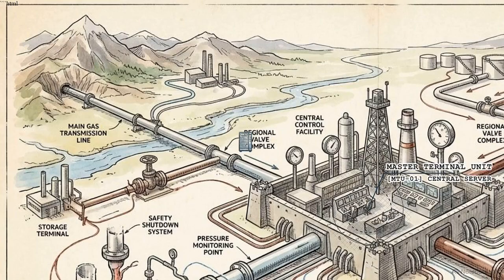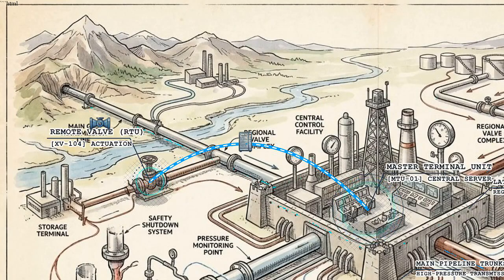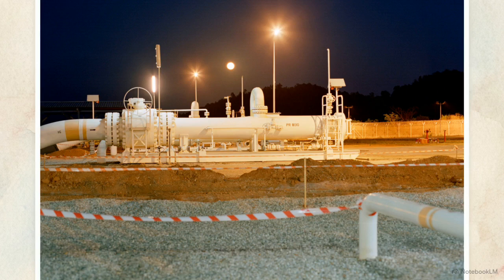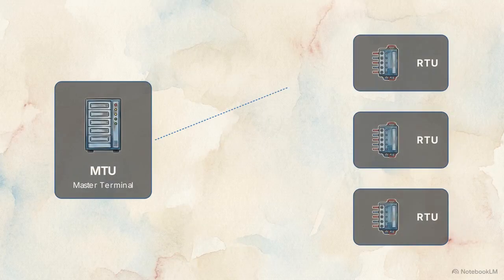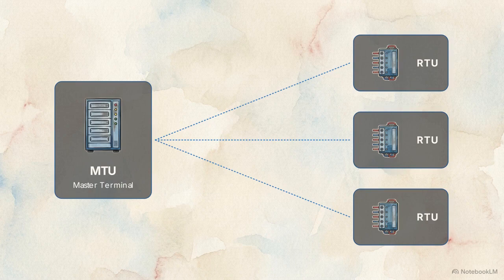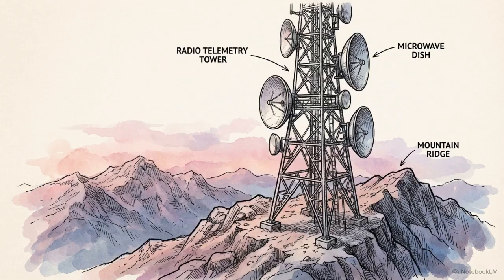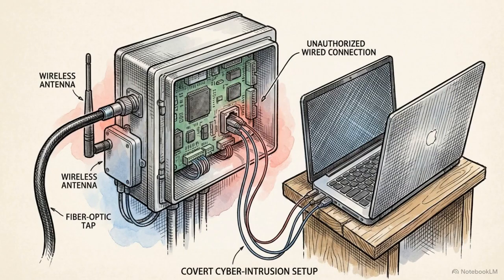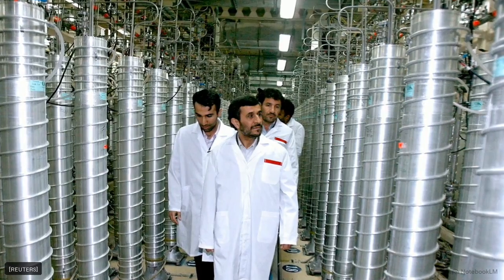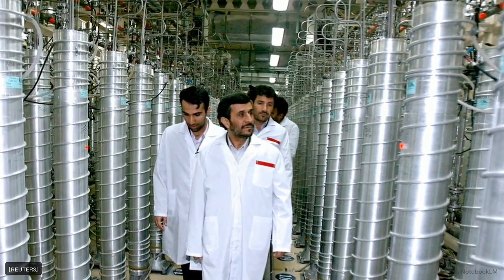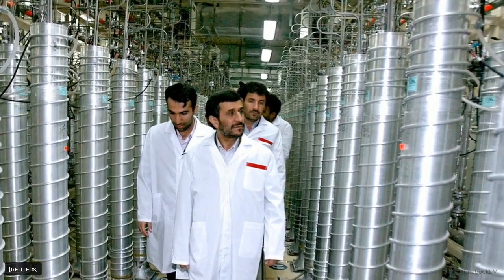The logic we've tracked applies to a single processing plant, but industrial infrastructure often spans hundreds of miles of pipelines and pump stations. Distributed operations require supervisory control and data acquisition, or SCADA, while a DCS controls a localized plant. SCADA utilizes a central master terminal unit to pull data from isolated remote terminal units spread across vast geographical distances. Because SCADA covers so much territory, it relies on cellular networks, satellite uplinks, and radio telemetry. Connecting industrial control hardware to these wider networks introduces severe cyber vulnerabilities. The 2010 Stuxnet worm proved that malicious code could physically destroy industrial equipment by infiltrating these networked automation systems.